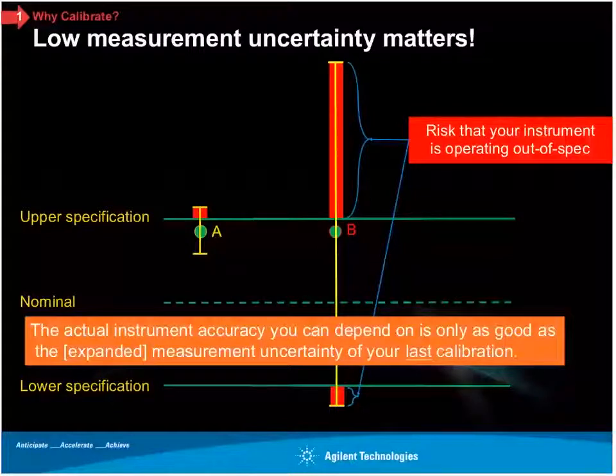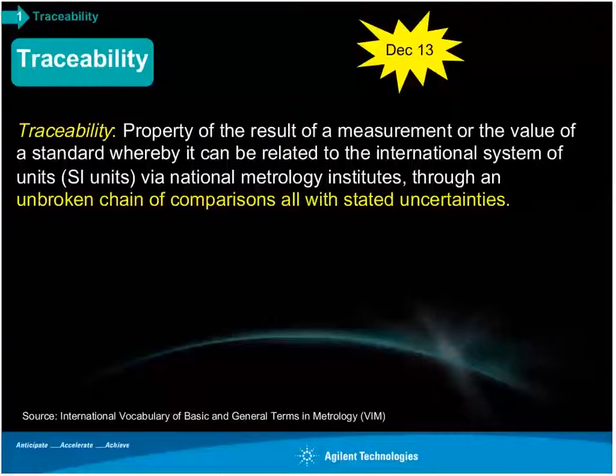So the last point in the review is this: the actual instrument accuracy that you can depend on as a user is not what's in the data sheet. Well, of course it is when you first get the instrument, but on an ongoing basis, after you're receiving it from a calibration, the actual instrument that you can depend on is really as good as the expanded measurement uncertainty of your last calibration. So that's really why that's so important.